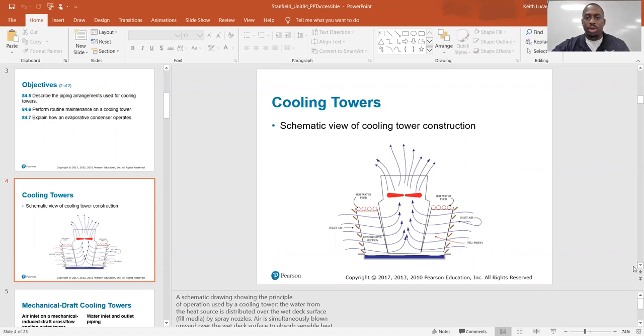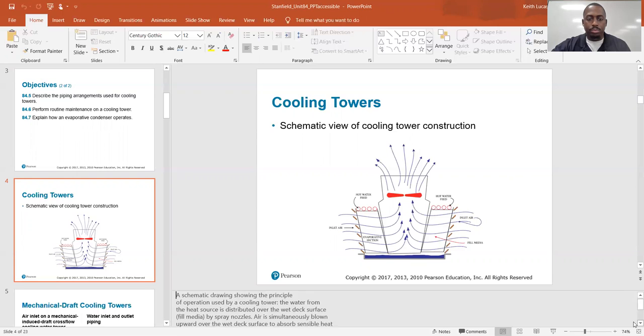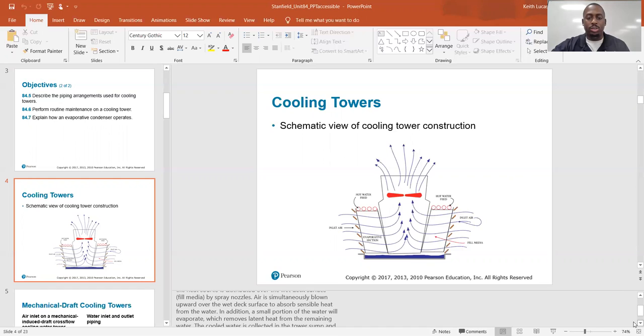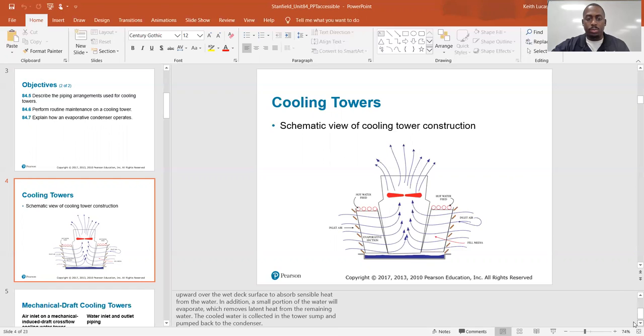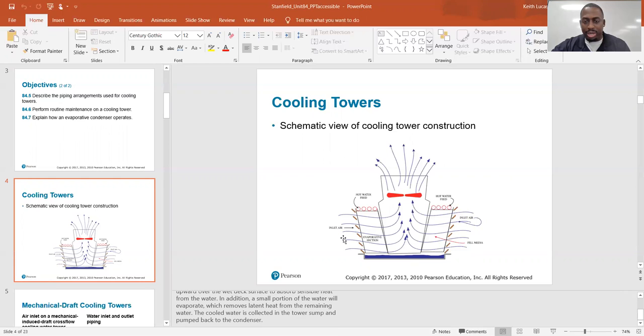Cooling towers — schematic view of cooling tower construction. A schematic drawing showing the principle of operation: the water from the heat source is distributed over the wet deck surface or fill media by spray nozzles. Air is simultaneously blown over the wet deck surface to absorb sensible heat from the water. In addition, a small portion of the water will evaporate, which removes latent heat from the remaining water. The cool water is collected in the tower sump and pumped back into the condenser. The outside ambient air is getting sucked in by this fan — this is an induced draft cooling tower.